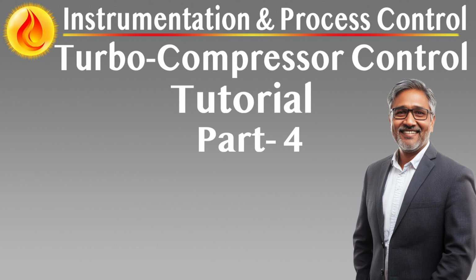HMI hardware platform: industrial PC-based architecture, housed within each unit control panel, UCP, built with rugged hardware capable of continuous operation under harsh conditions. Operating system and software: based on Microsoft Windows 2000 or XP, configurable to modern platforms. Uses industry-proven SCADA or HMI software with support for OPC and Modbus data interfaces.